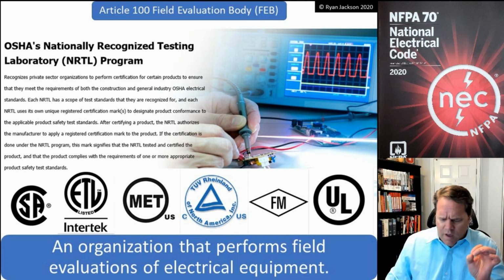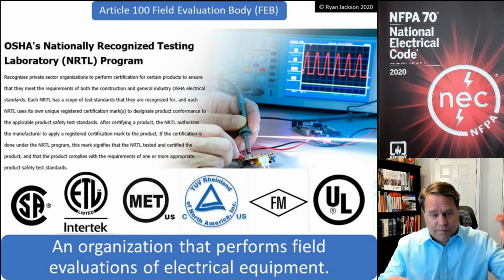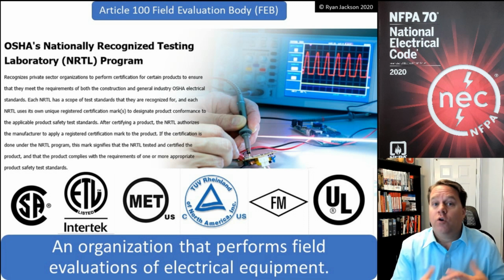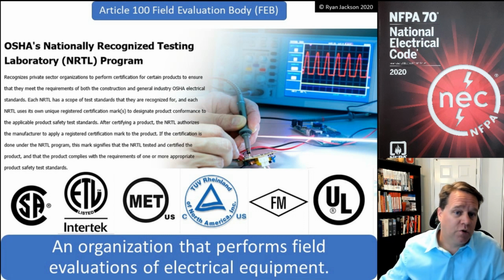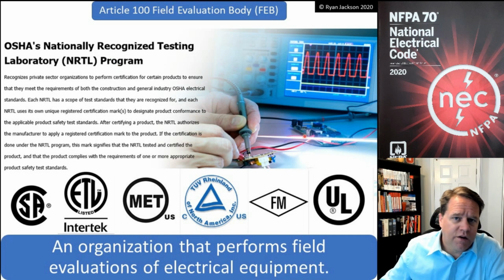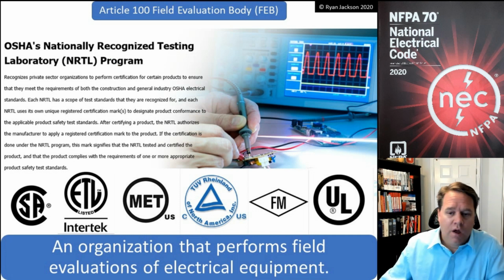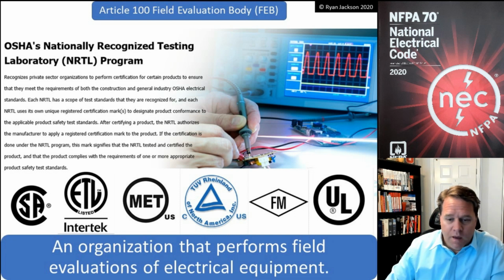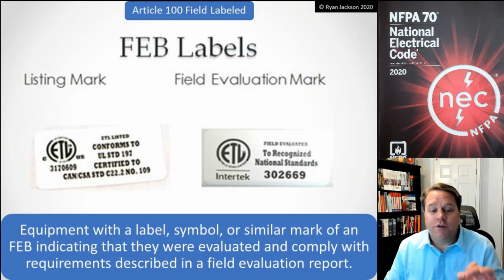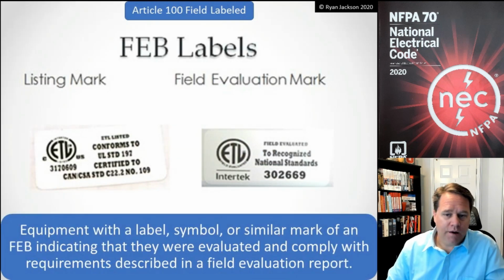In fact, if you want to find the de facto list of certified testing bodies, what OSHA calls nationally recognized testing laboratories, go to OSHA's website and search for NRTL, Nationally Recognized Testing Laboratory. There is a whole bunch of different bodies that will do field evaluations and product testing. So that's the field evaluation body. I would hire a field evaluation body to perform a field evaluation and hopefully get a field label applied.